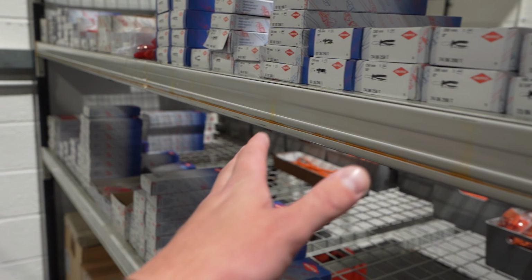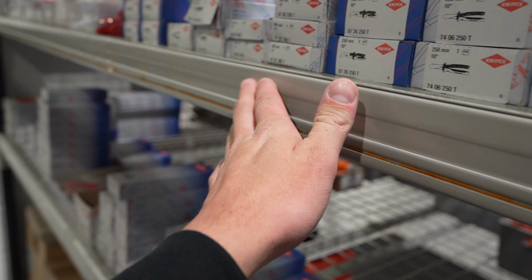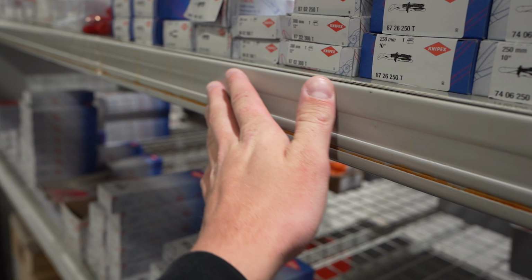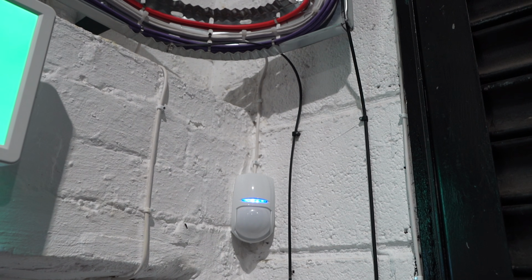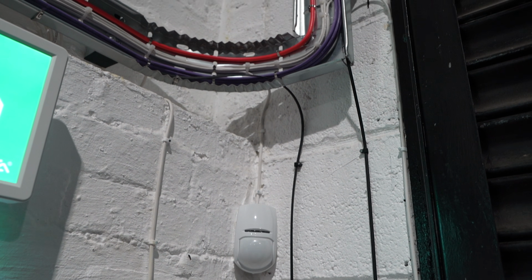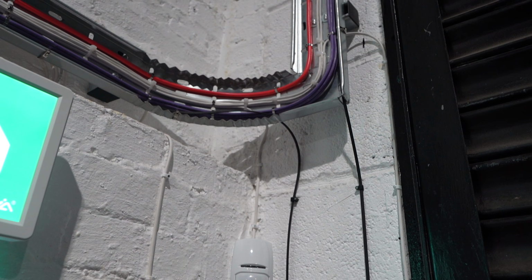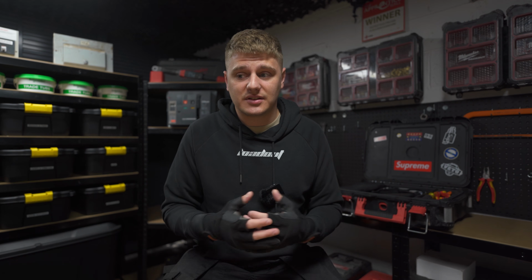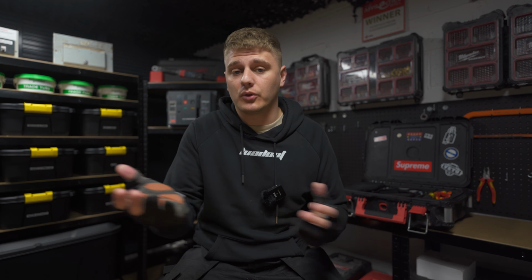It's also important to determine whether something is in fact an exposed or extraneous conductive part. If it's an unnecessary bond, you may be allowing faults to be exported to parts of the installation and basically allowing current to flow in areas of the installation where it simply wouldn't be present if you didn't bond it in the first place.